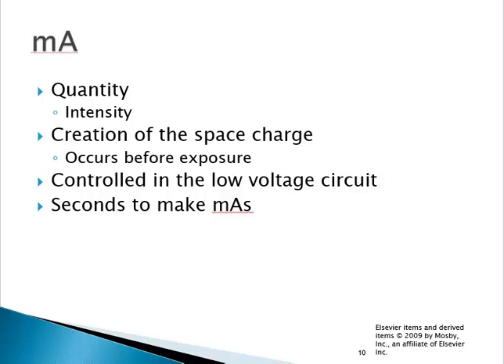When we set our MA selector, it goes into the step-down transformer, giving us low voltage and an amperage of 3 to 5 amps. We don't have MAS until we make our exposure and send the electrons across the tube. At that point we apply the seconds, and the seconds represent the length of time that electrons are traveling across the tube at any given MA.